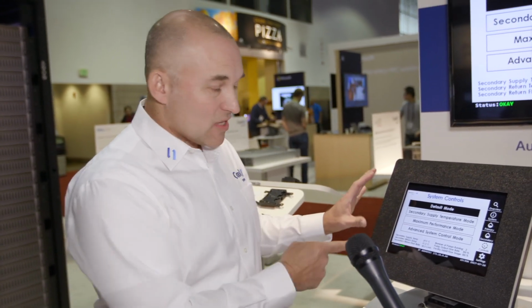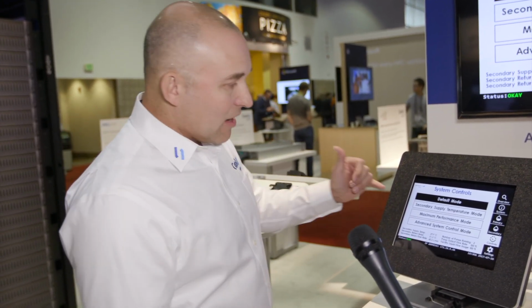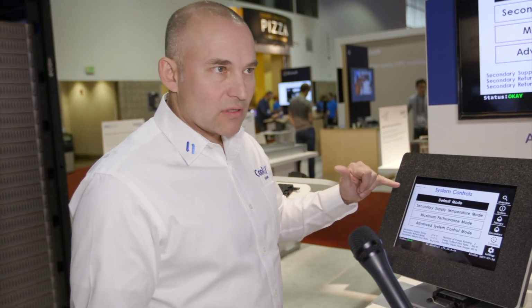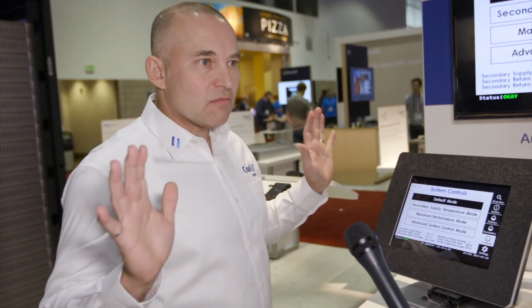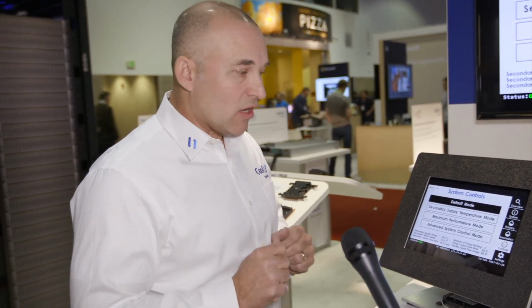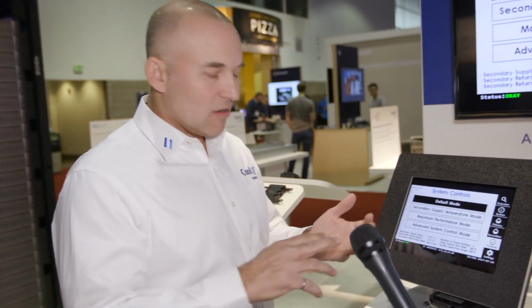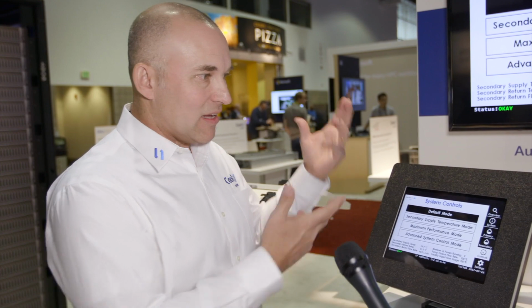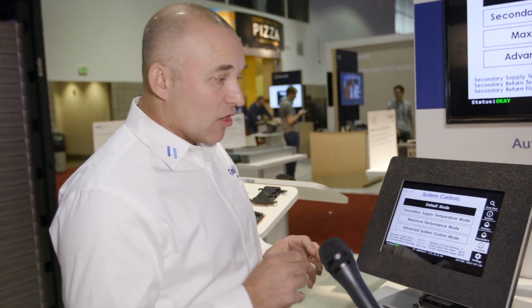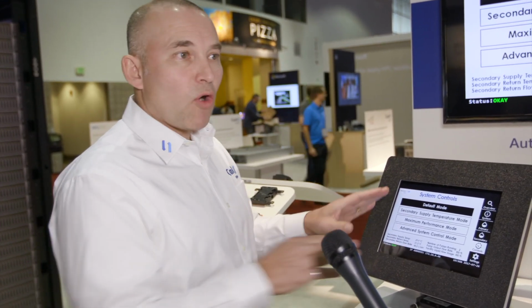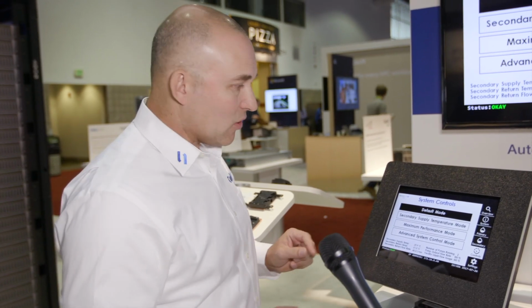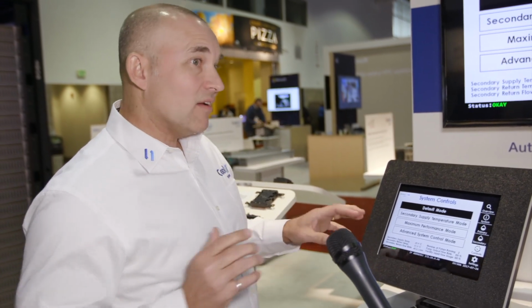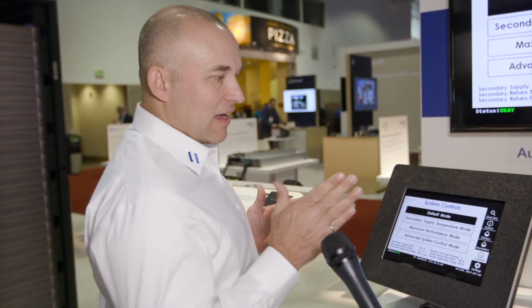Like when we're talking about, this is actually for the CHX80, you have the ability for it to just run on default. And in default mode, it's autonomous, lights out. So it'll automatically guarantee that you're not going to go below dew point and have condensation inside the server rack. It'll also ensure that there's only appropriate amounts of flow, right? So it monitors the pressure of the outlet compared to the inlet, right?